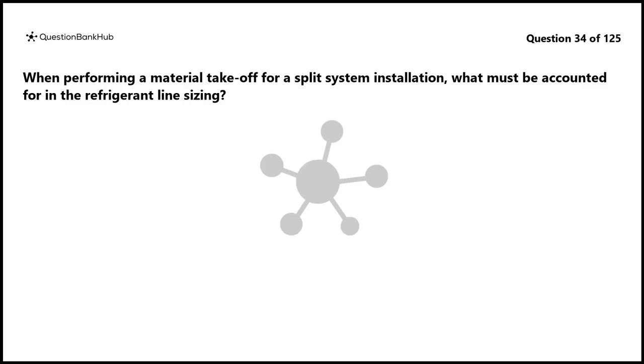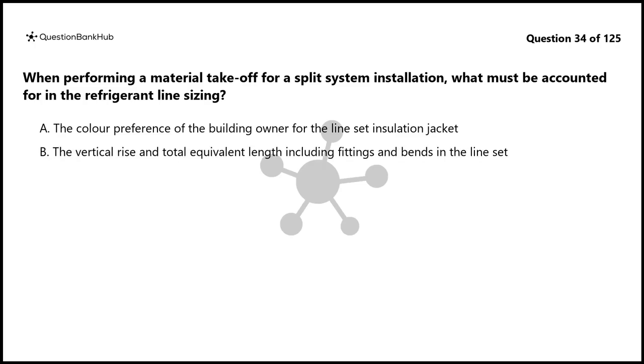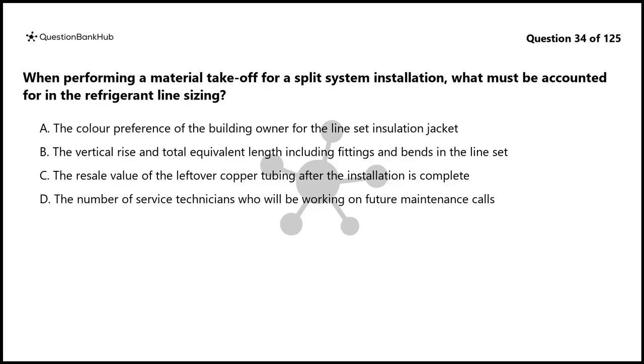Question 34. When performing a material takeoff for a split system installation, what must be accounted for in the refrigerant line sizing? A. The color preference of the building owner for the line set insulation jacket. B. The vertical rise and total equivalent length including fittings and bends in the line set. C. The resale value of the leftover copper tubing after the installation is complete. D. The number of service technicians who will be working on future maintenance calls.